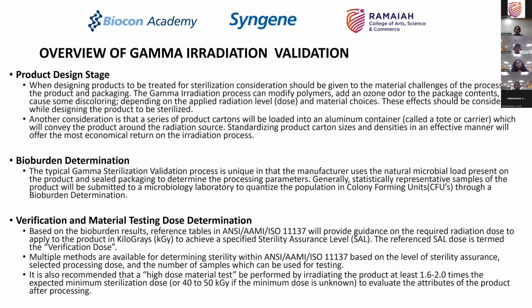And based on this, general guidance is provided saying that, okay, you can use 25 kilograys, or you can use 15 kilograys, or you need to use a higher number of kilograys so that you achieve the required sterility dose. So first is to determine the dose. Now, multiple methods are available for determining sterility within the guidelines, based on the level of sterility assurance, selected processing dose, and the number of samples which can be used for testing. So there are methods provided in the ISO 11137 guidelines saying how you determine whether the product has become sterile. Okay.